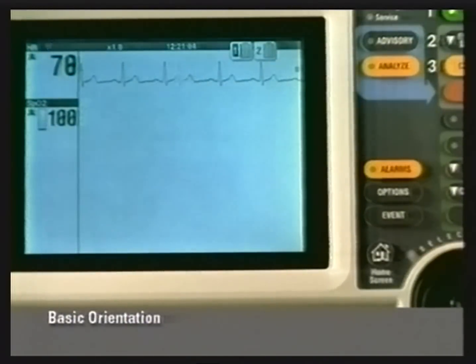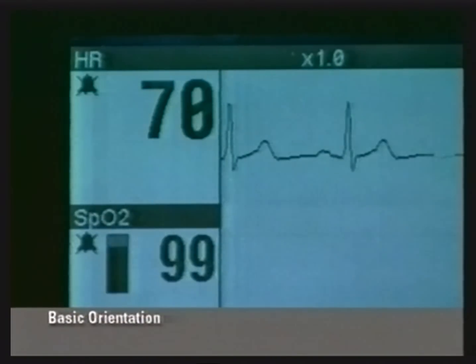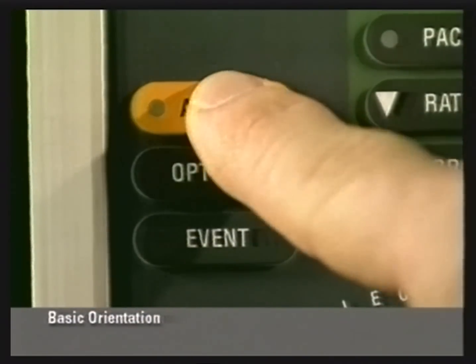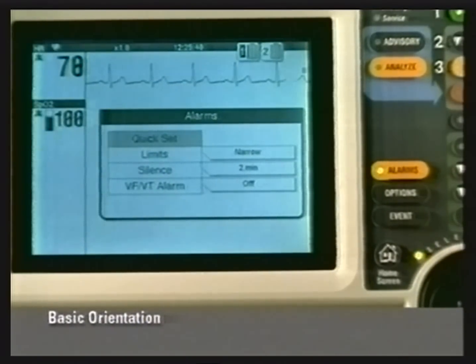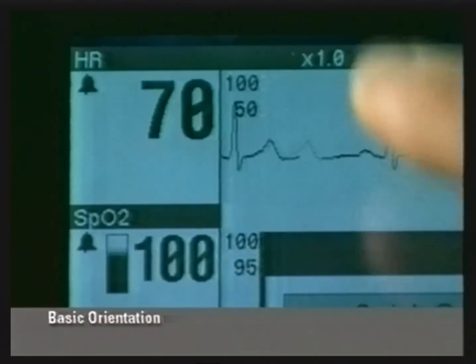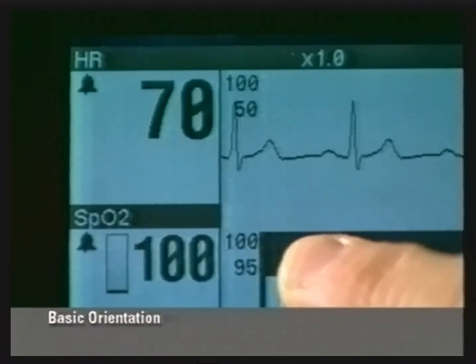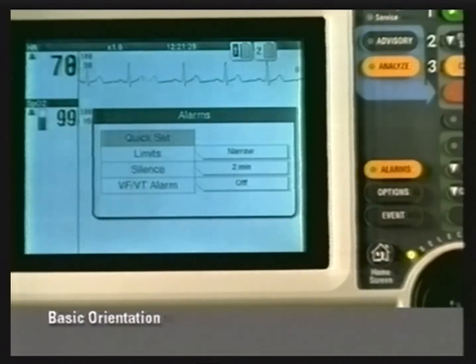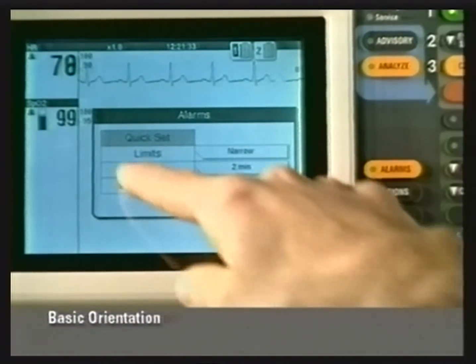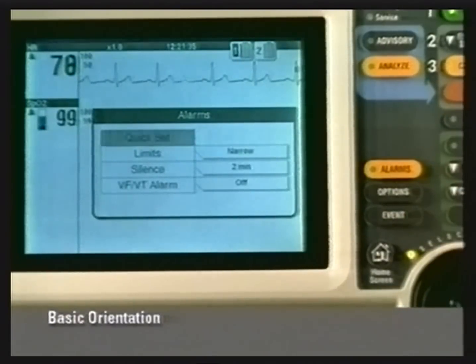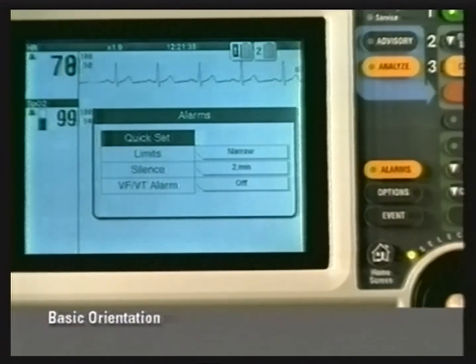The Lifepak 12 defibrillator monitor features quick-set alarms. Quick-set alarms can be configured to be on or off when the defibrillator is powered on. If quick-set alarms are configured off, push Alarms to activate the alarm. The Alarms menu appears. When activated, Quick-set automatically sets alarm limits around the patient's current vital sign values for all monitored parameters. If the limit setting is acceptable, press the selector. Quick-set highlights in black and a bell symbol next to the monitor parameter indicate alarms are active.